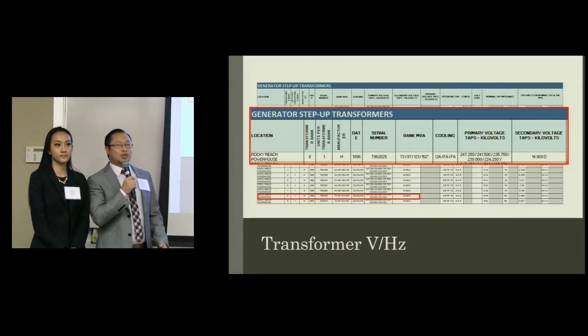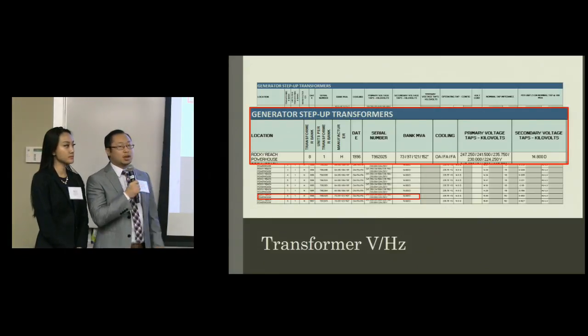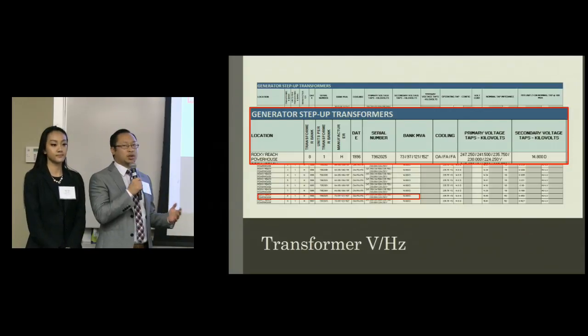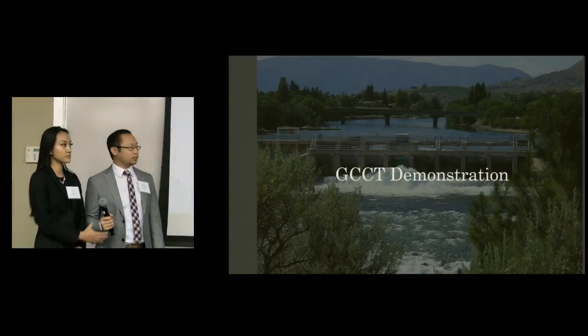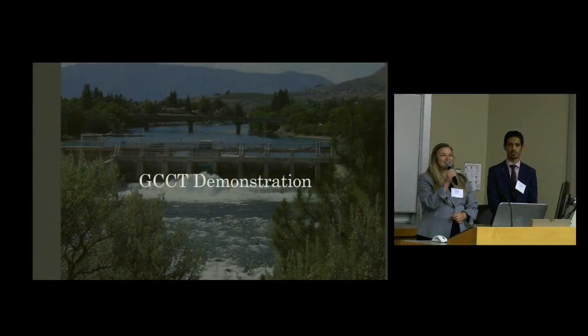transformer rating with respect to the generator base to be 1.0 per unit for this value. With that, we can plot the transformer volts per hertz limit the same way we plot the generator volts per hertz limit. Now we can move into a demonstration of the GCCT.